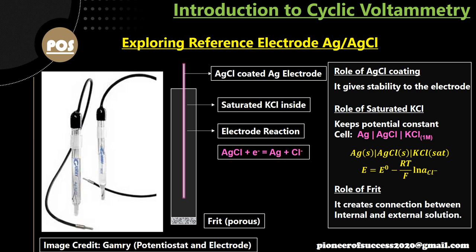There are multiple reference electrodes, but I took the example of Ag/AgCl for this video. There are three parts in a reference electrode: one is an AgCl-coated Ag electrode — a wire dipped inside a chamber; the chamber contains KCl potassium chloride saturated solution; and at the bottom there is a porous plug called a frit. So a reference electrode has three parts: AgCl-coated Ag wire, a chamber with KCl saturated solution, and a porous plug called frit at the bottom.